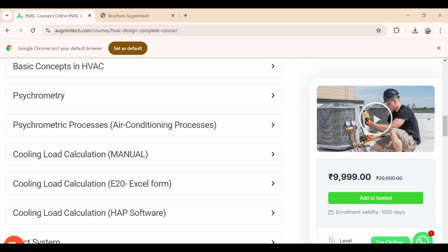Sir, we have 8 diffusers here. You have a calculator for only a single outlet, but where will we calculate for all outlets? Do we have to consider the previous velocity, for example, in the first branch, the main branch, we have 8,000 CFM, and from there we are supplying 1,000. So do we have to consider 3,000 FPM as V1? Please explain. That, all I have explained in detail.